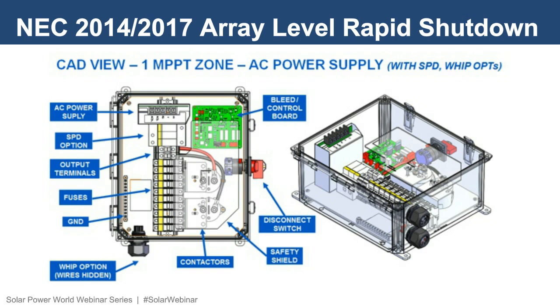On the right side of the enclosure, you'll see the 2 contactors. These contactors provide the isolation from the source circuits to the output circuit wiring. These contactors open up when a rapid shutdown is initiated, and thus isolating the home run segment of conductor between the combiner and the inverter. Additional electronics in this box include the bleed and control board, as well as the AC power supply. The AC power supply is where you'd interface the control power, control signal circuit to allow you to initiate the rapid shutdown. On the right is the disconnect switch, allowing you to locally disconnect the combiner box.